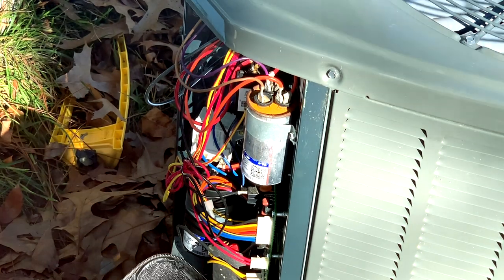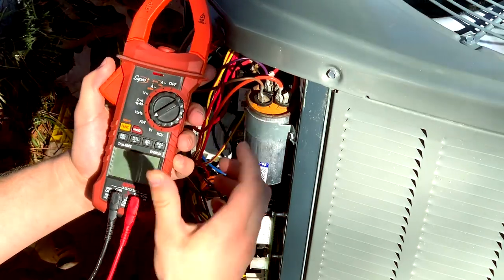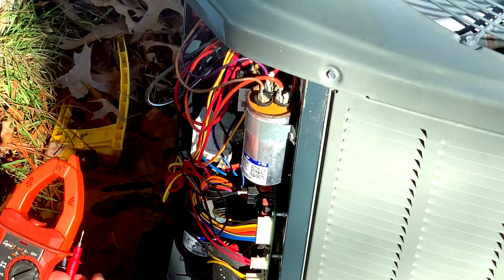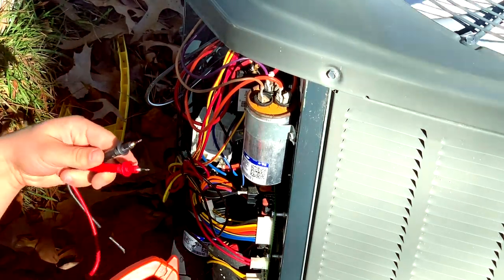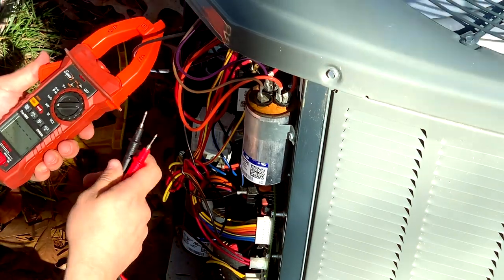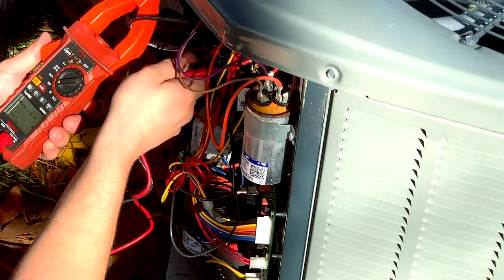We're going to have to check amperage and volts together at the same time. Set it to volts, and I measure the voltage on the load side of the contactor on the outdoor unit. We would take our compressor common winding and our voltage on the top of the contactor here.